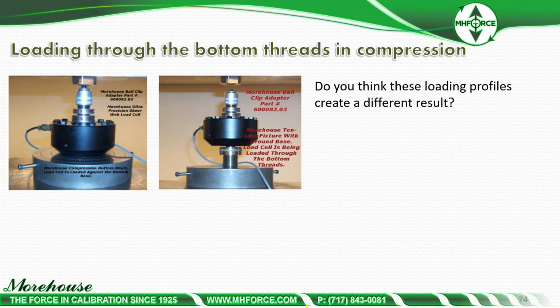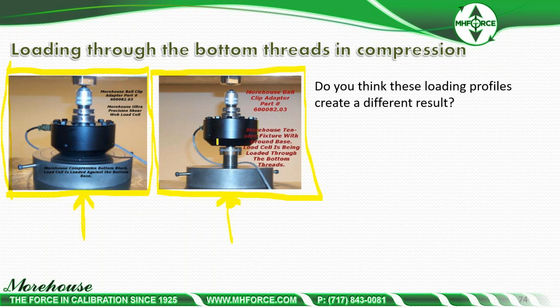This one's not a bad thing; it's just something you need to be aware of. So we load. Typically, we're finding about 99% of our customers want to load a load cell this way. That's fine. Nothing is wrong with that, right? If that is you, if you are in the 95%, congratulations. That is our default loading procedure. However, that other 1% want to load it this way. As long as we know and we replicate how it's being used, we're okay. Our competitor, as their standard, they load it this way. They load it the way on the right.